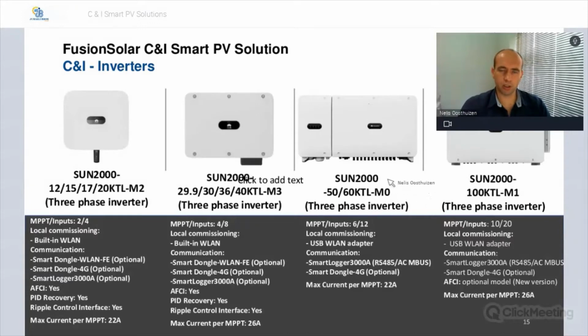So going over to the larger segments of commercial and industrial. So the 50 and 60 kTL, the difference between them and the previous ones is now you've got 6 MPPTs with a total of 12 strings input. So you will note that as the size of the inverter is increasing, you've got more MPPTs. So what this allows you is a saving, because you don't need to add an extra combiner box to then take a single string or 2 strings to your inverter. The inverter has got multiple MPPTs, so it's actually a saving on your capital expenditure.